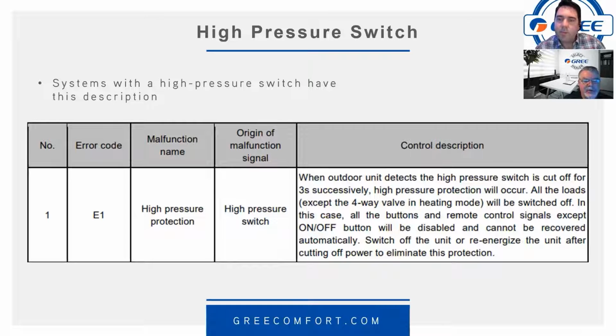So then high pressure switch. If the system has a high pressure switch and it trips, the entire unit shuts down. This is the description out of the service manual. When the outdoor unit detects high pressure, the switch is cut off for 3 seconds successively. High pressure protection will occur. You get the E1. All loads except the 4-way valve, which is energized in heating, will be switched off.